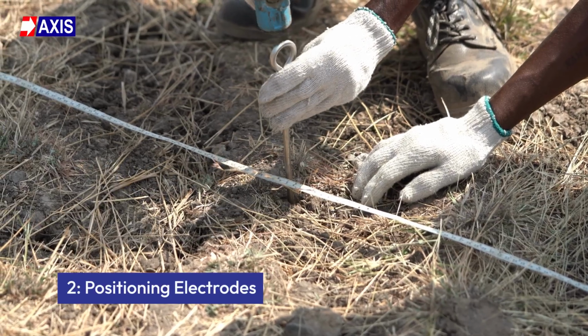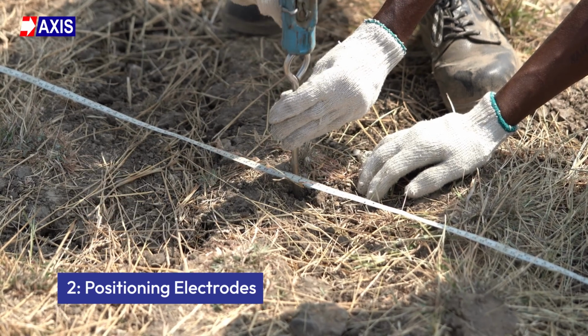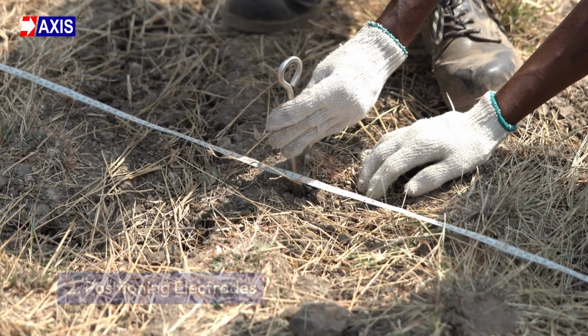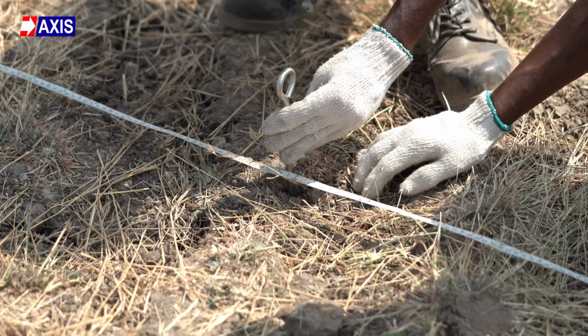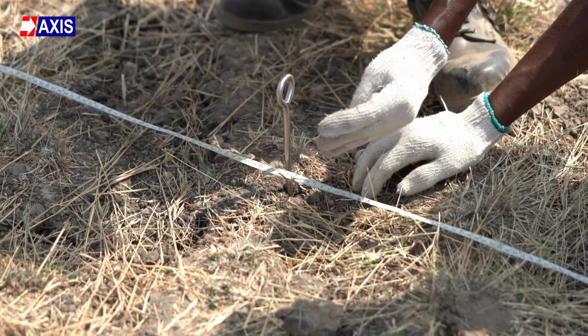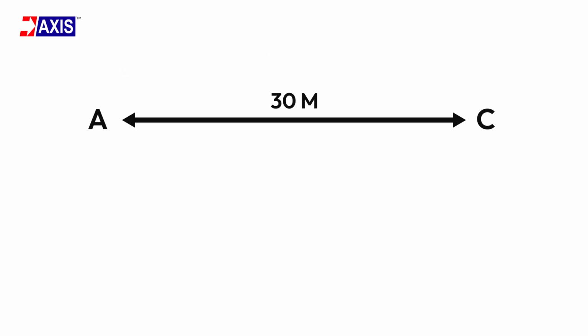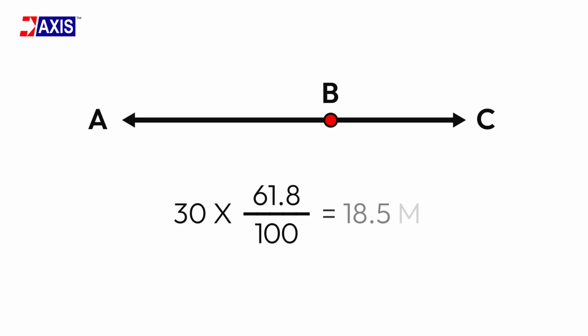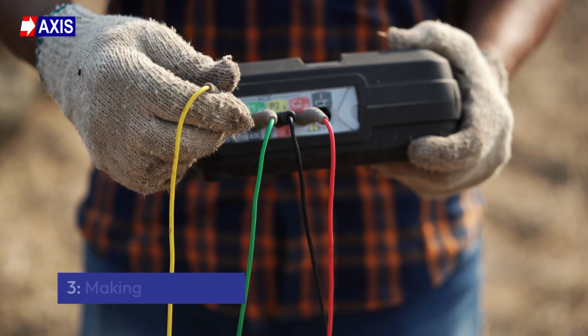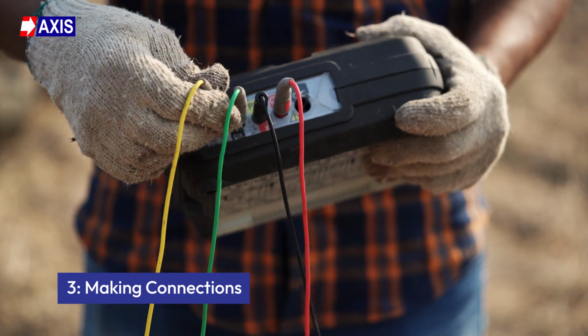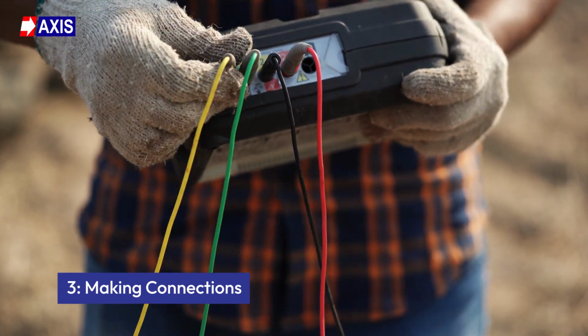Step 2. Positioning of electrodes. Position the potential electrode. Place electrode B at 61.8% of the distance between A and C. If A and C are 30 meters apart, place electrode B approximately 18.5 meters from A. Step 3. Making connections. Connect the test equipment to the electrodes as shown here.